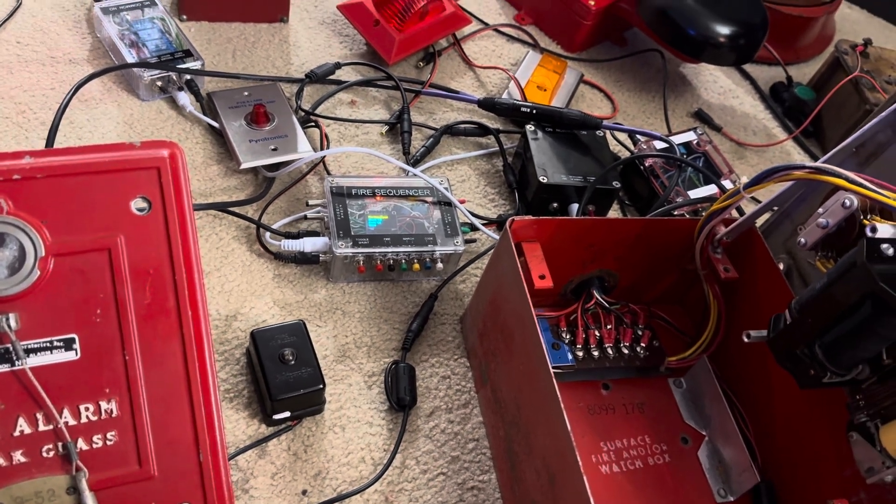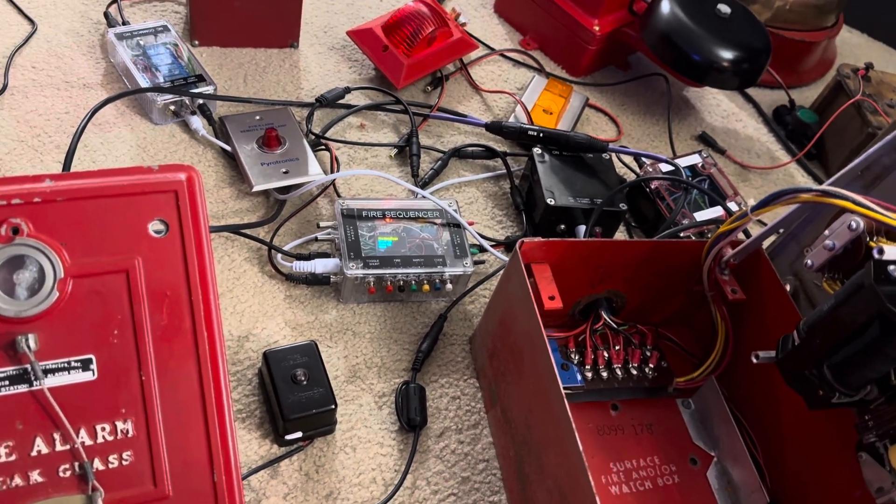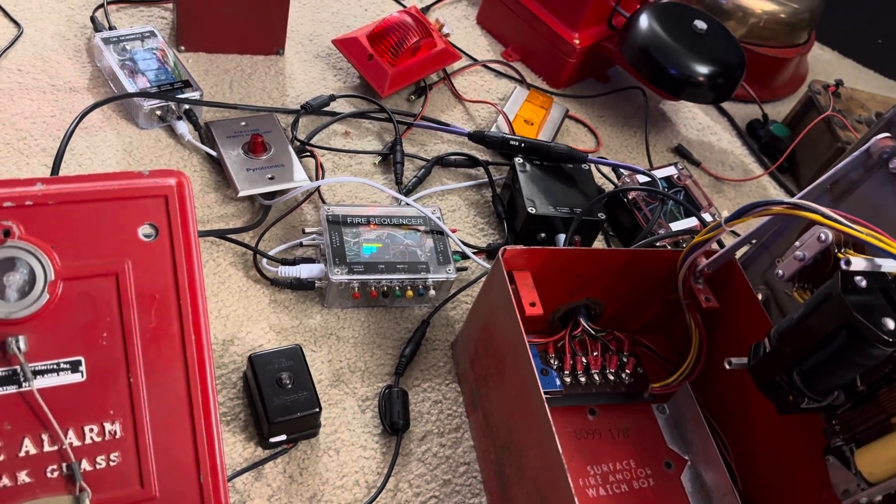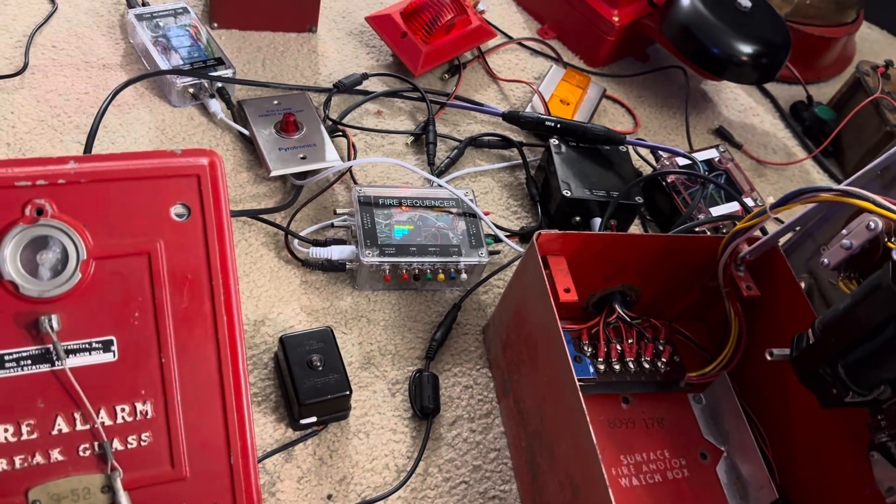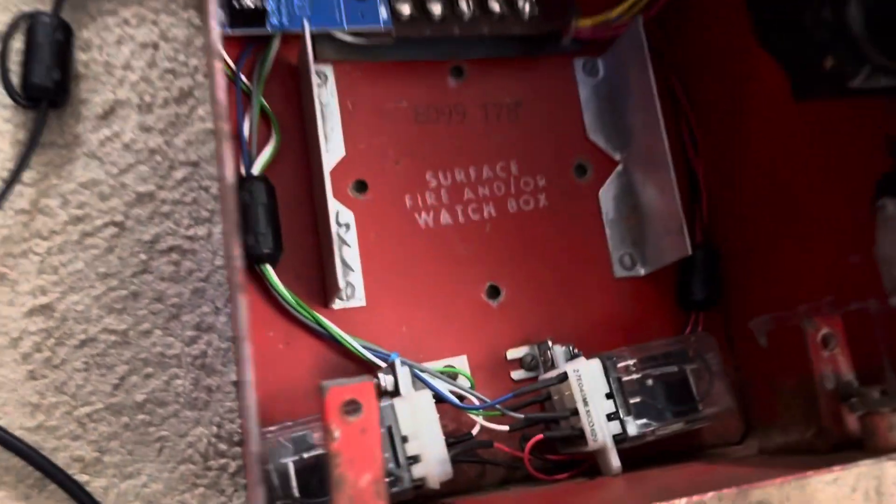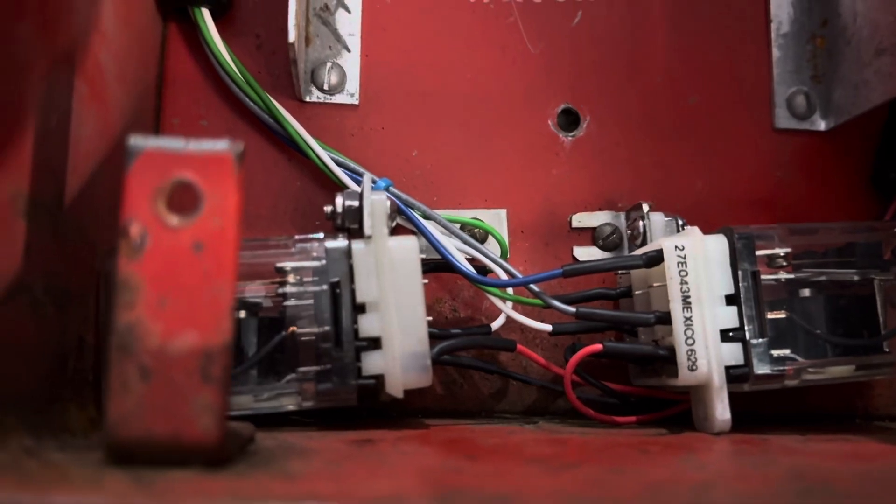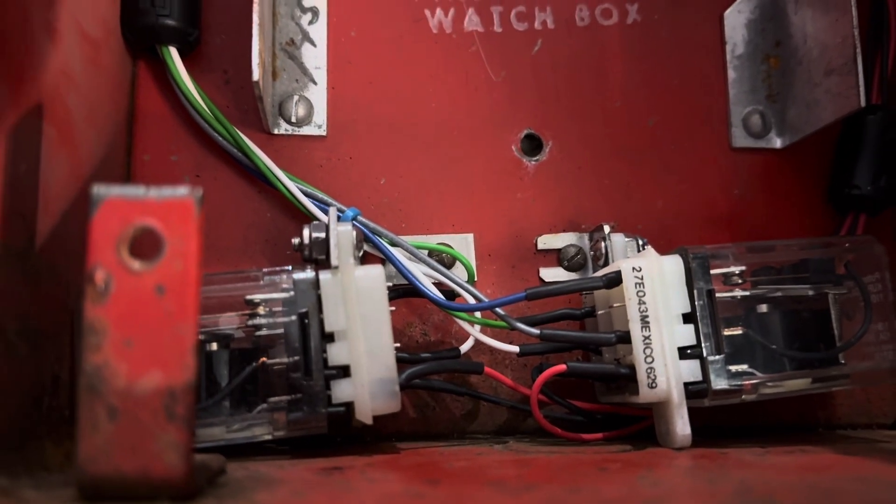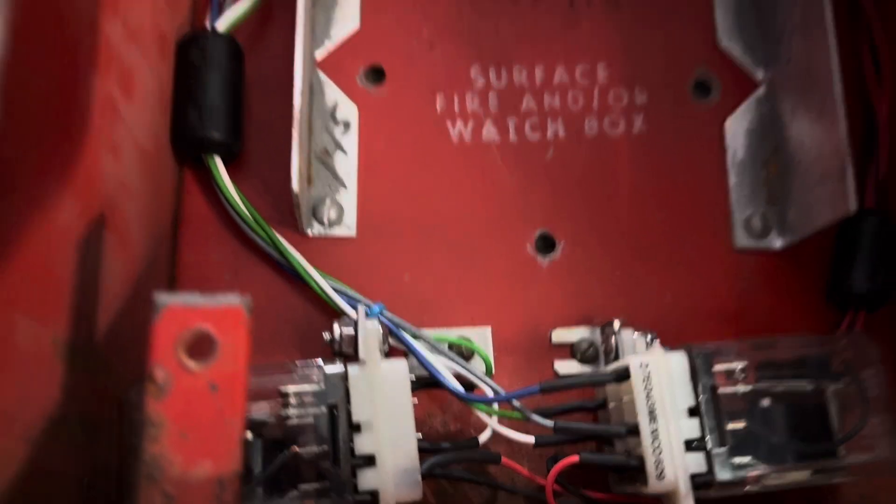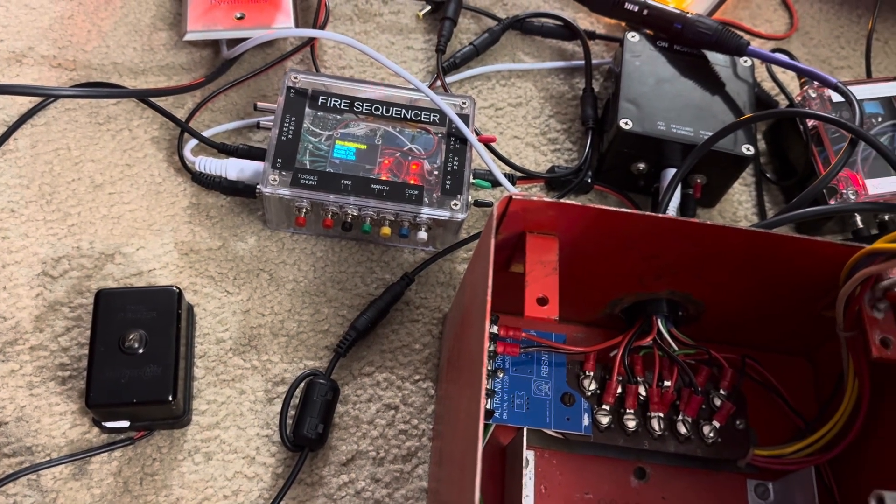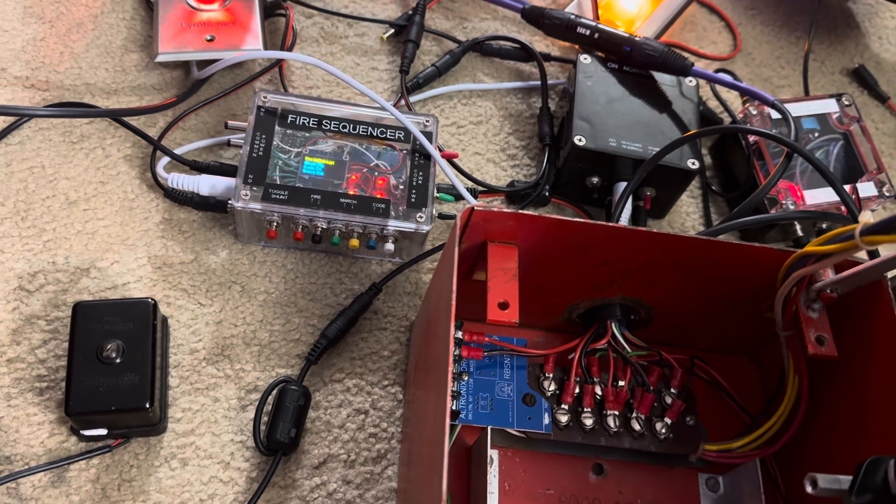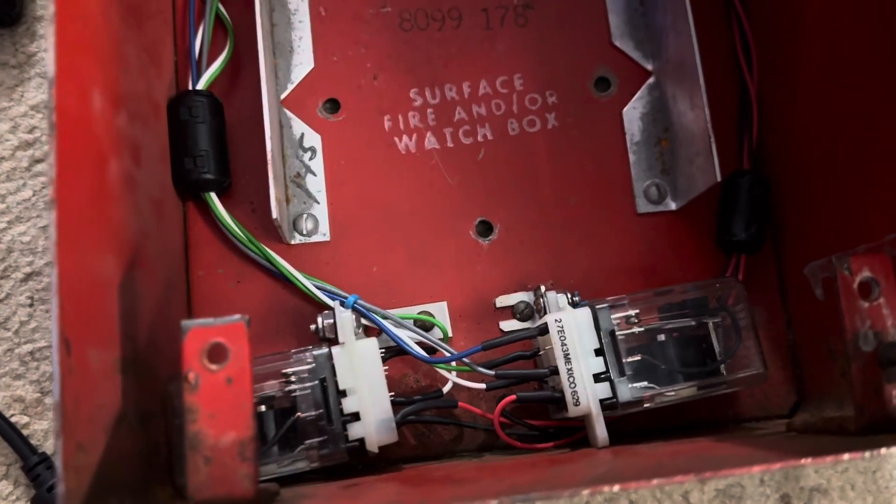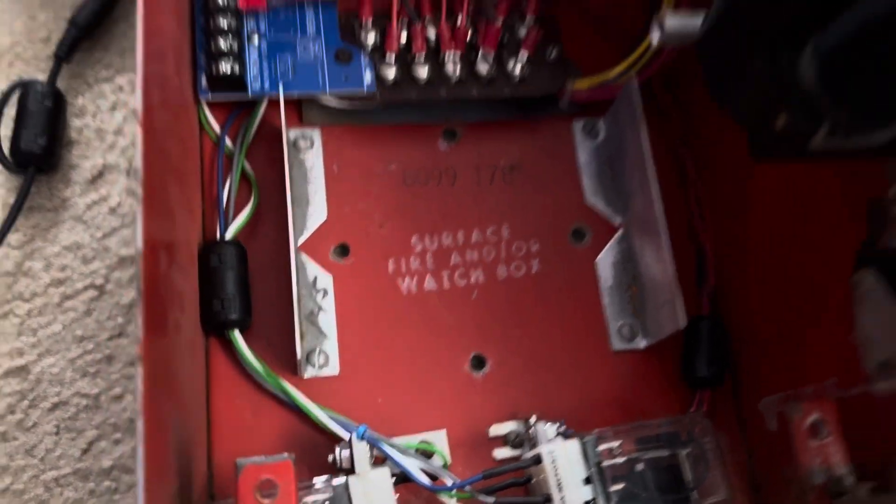The way it actually cuts power between stations is whether the power is going back the other direction. And the way the panel knows that it's in alarm is that the power does not return to it. So let me explain. Right now, this relay here is being closed through supervisory power. If I unplug the circuit, I get supervisory alarm and the oscillator is running, which is what it would have done on the real panel.